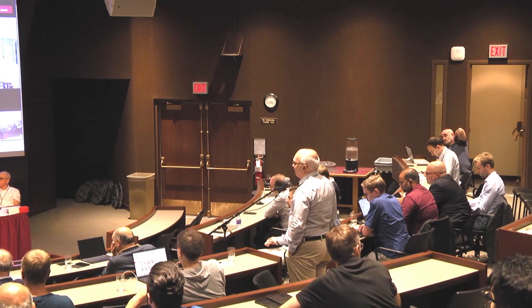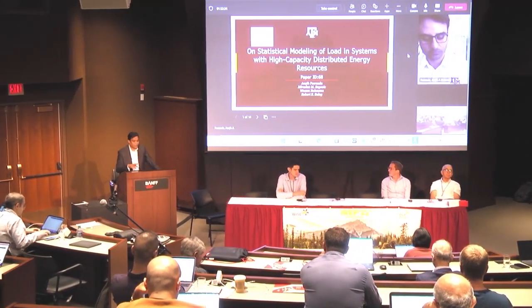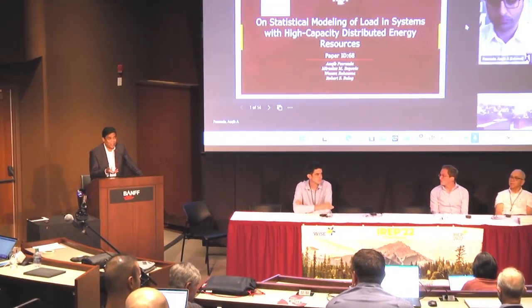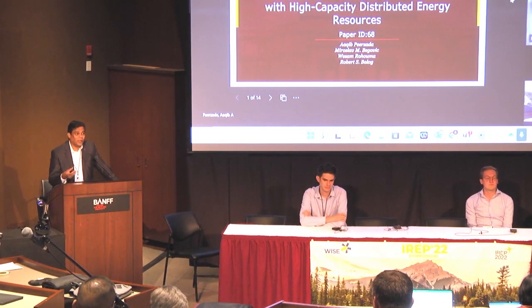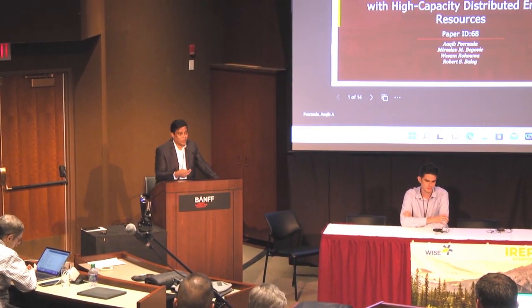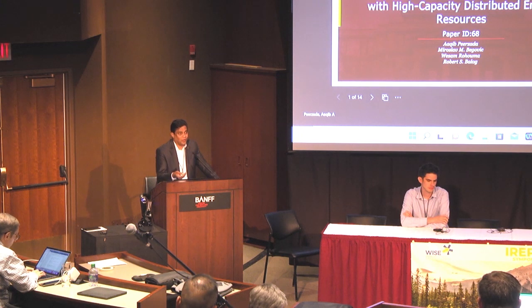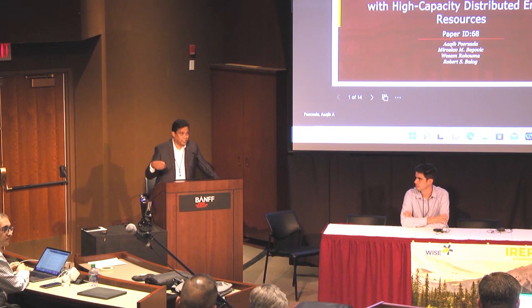So our next step is to do state estimation with the bus branch models, the network topology. At this point in time, we are only building the substation configuration. Usually, the state of the art is that the breaker status is communicated with SCADA. But here we are saying, can we use voltage and current measurements to infer the substation configuration to help us build the bus branch model, and eventually the network transmission topology, which can be used in state estimation.